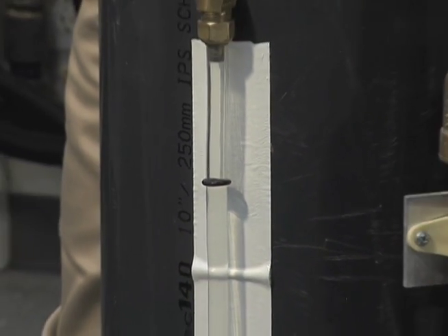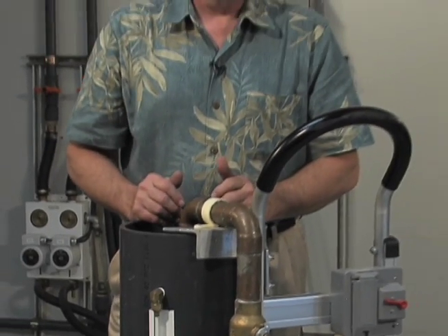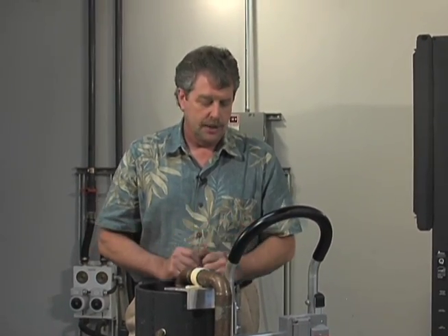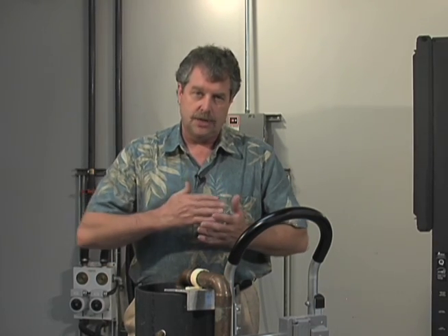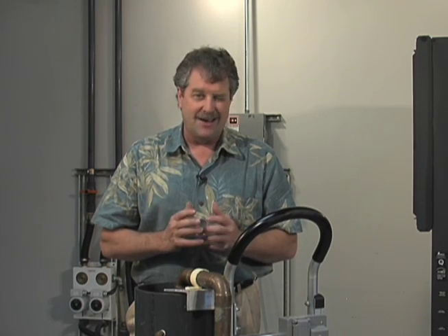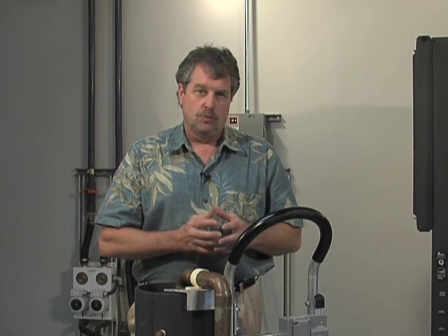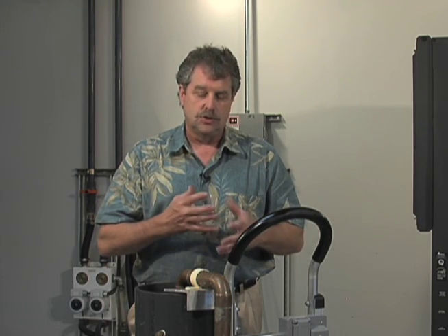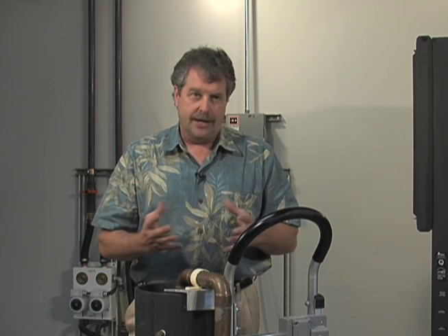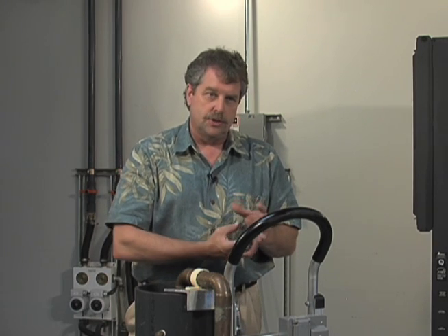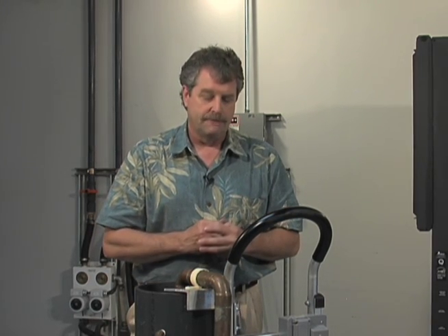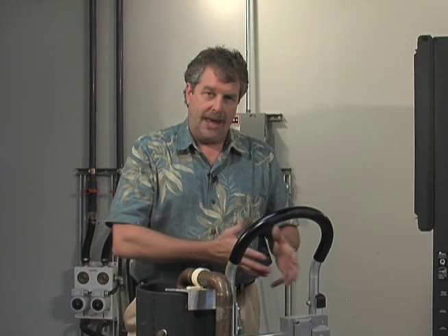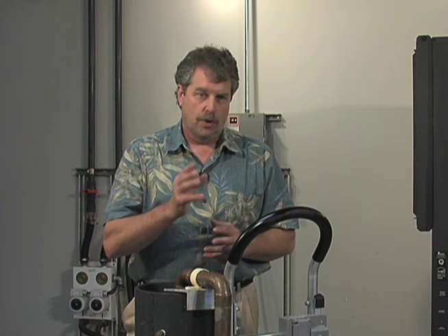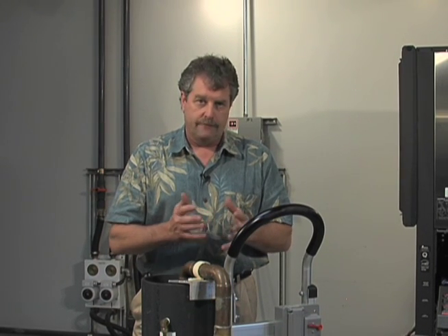Now, if you have a system where you're getting a much more significant drop in fluid level, that means you have a lot of air. And if you can't seem to move it out by going through a series of deadheading processes, in other words, throwing that valve closed, waiting until that pressure gauge gets up to that sweet spot, then throwing that valve open. If you can't move it out, and sometimes that's a vertical bore system where the U-bends were installed with water in them, but the surface piping that was installed to tie in your bore field still has air in it, it's difficult to force that air back down through the U-bends, dislodging that water and getting it all flushed out. It can be a bit challenging. So what you'll need to do is use your pump and your municipal water source and do what we call a power flush. We're going to make that a separate video segment, which you'll be able to watch a little bit later.